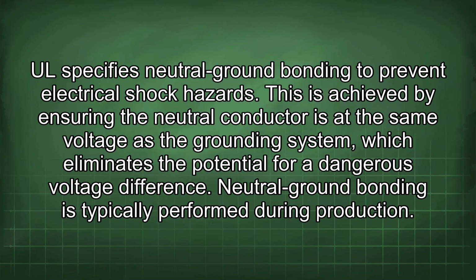UL specifies neutral ground bonding to prevent electrical shock hazards. This is achieved by ensuring the neutral conductor is at the same voltage as the grounding system, which eliminates the potential for a dangerous voltage difference. Neutral ground bonding is typically performed during production.